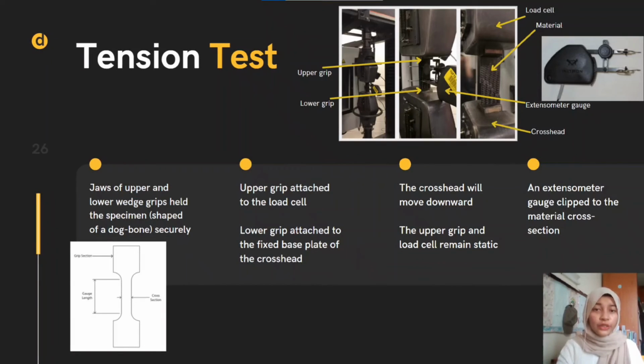During the tension test, the material, typically in the shape of a bone as can be seen in the picture, is held securely in the jaws of upper and lower wedge grips. In the standard configuration, the upper grip is attached to the load cell, while the lower grip is attached to the fixed base plate of the crosshead. And then the crosshead will move downwards, while the upper grip and load cell remain static. And the last one is that an extensometer gauge may be clipped to the material cross section to record a more accurate strain measurement, as can be seen in the picture above.